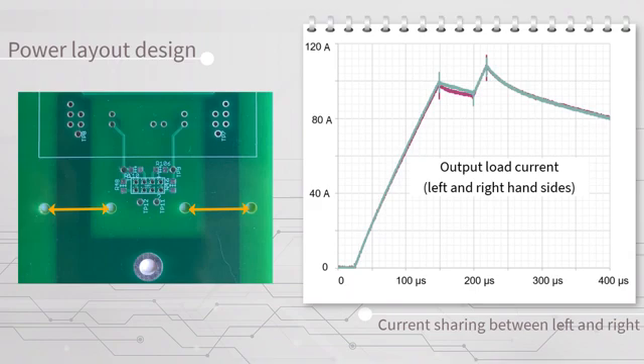Measuring the output load current in the module left and right halves shows very good current sharing.